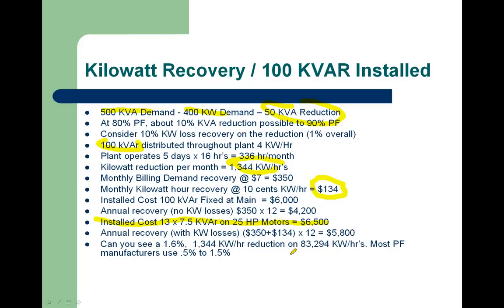Now, the main question that one would have, or at least I have, is whether you could actually see a 1.6% reduction in 83,000 kilowatt hours. If you look at your hydro bills over a year, you're going to find that the kilowatt hours range greatly from month to month. And trying to say, yes, I have saved 1.6% or 1.3% or 0.8% in kilowatt hours, it's really more of a calculation, and it's not really a measurable value. Whereas the kilowatt or kVA demand reduction on your hydro bill is very easy to see because your kVA actually reduces and your power factor increases.